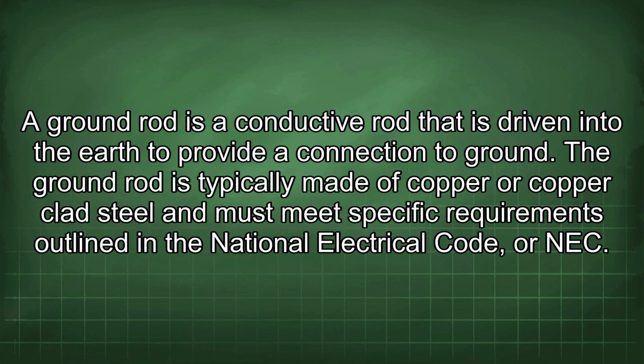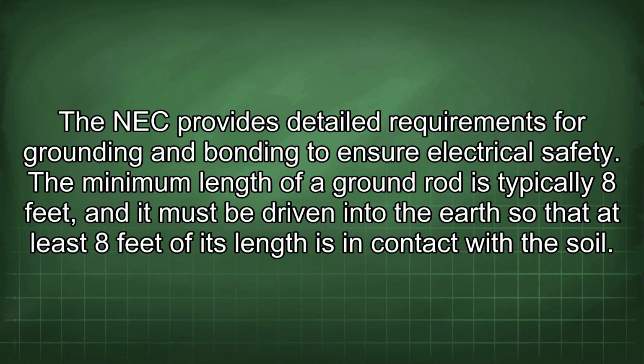A ground rod is a conductive rod that is driven into the earth to provide a connection to ground. The ground rod is typically made of copper or copper-clad steel and must meet specific requirements outlined in the National Electrical Code, or NEC. The NEC provides detailed requirements for grounding and bonding to ensure electrical safety. The minimum length of a ground rod is typically 8 feet, and it must be driven into the earth so that at least 8 feet of its length is in contact with the soil.